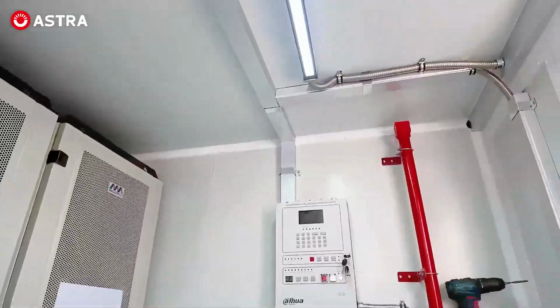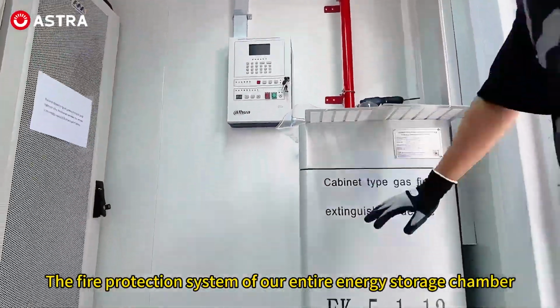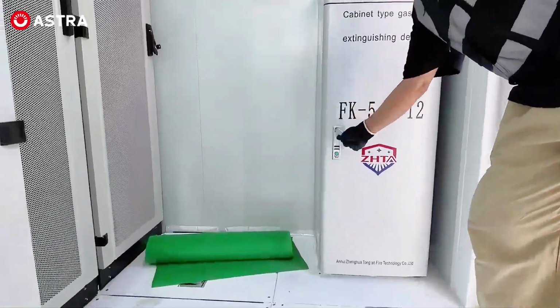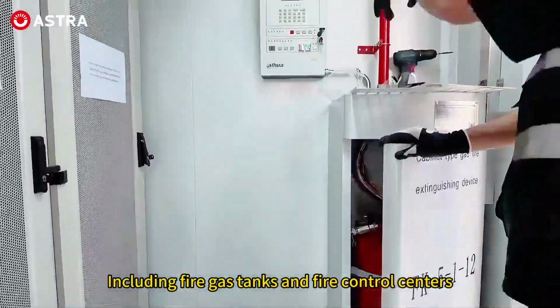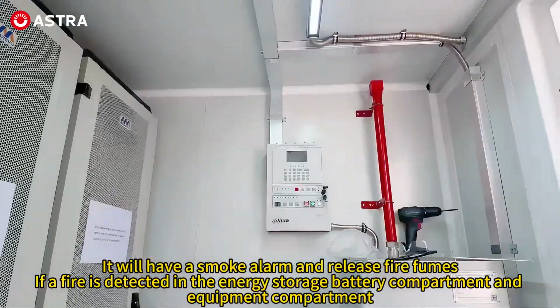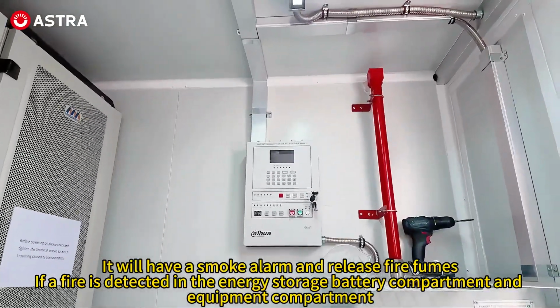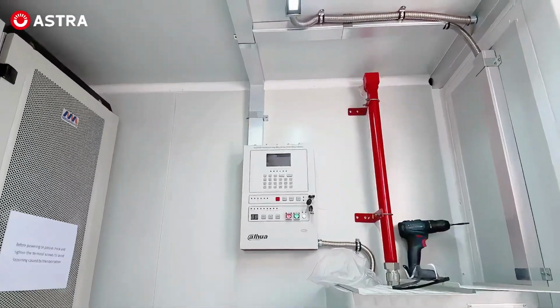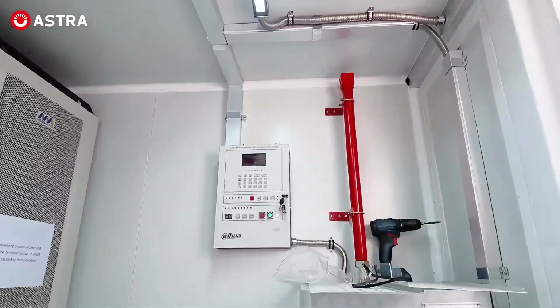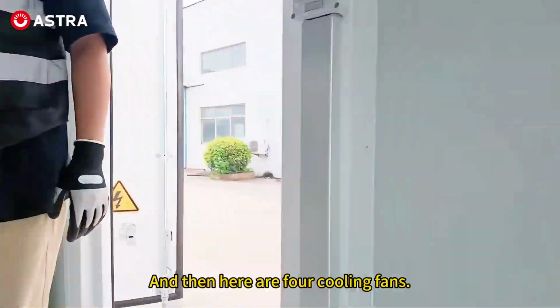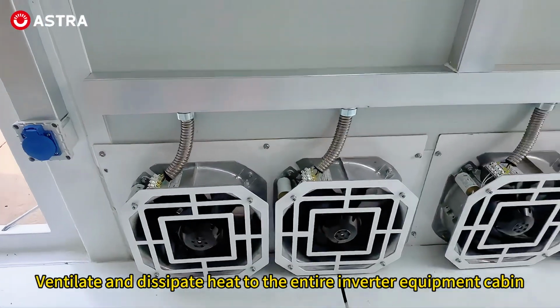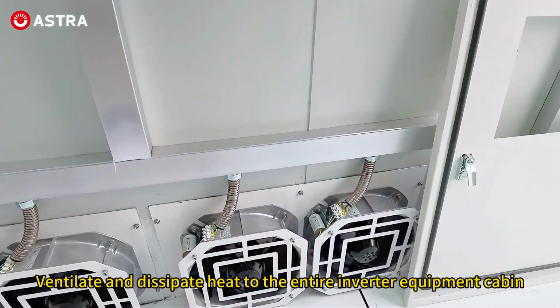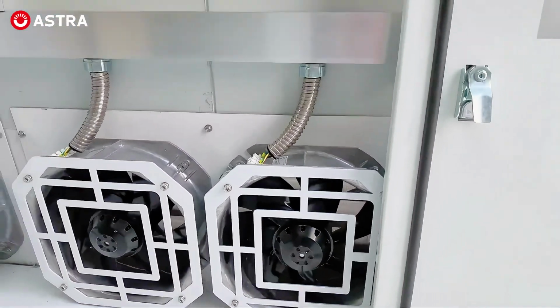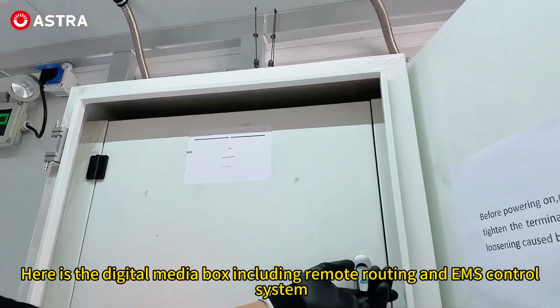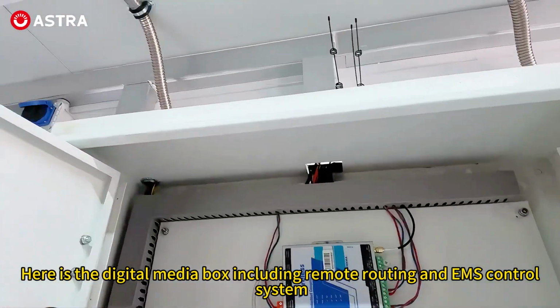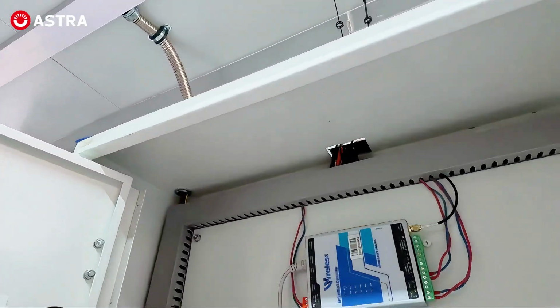Then you can see that on the right, the fire protection system of our entire energy storage chamber, including fire, gas tanks, and fire control centers. It will have a smoke alarm and release fire fumes if a fire is detected in the energy storage battery compartment and equipment compartment. And then here are 4 cooling fans. Ventilate and dissipate heat to the entire inverter equipment cabin. Here is the digital media box, including remote routing and EMS control system. This is the surveillance camera.